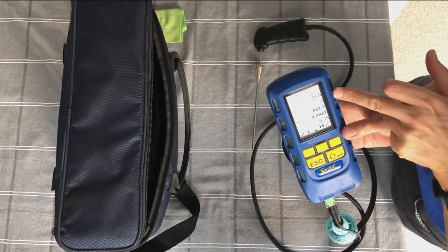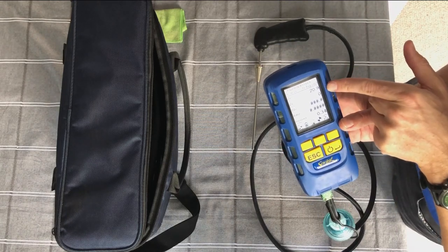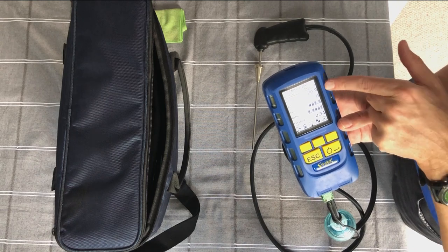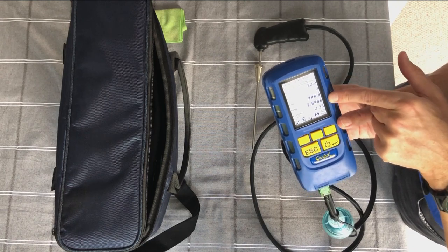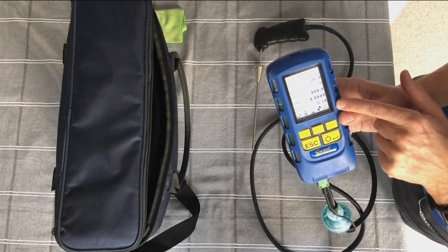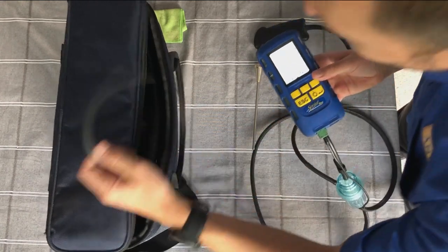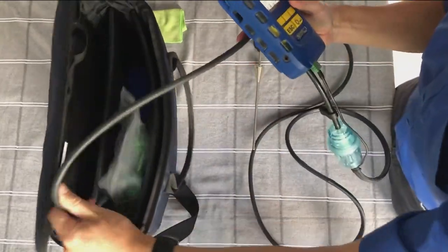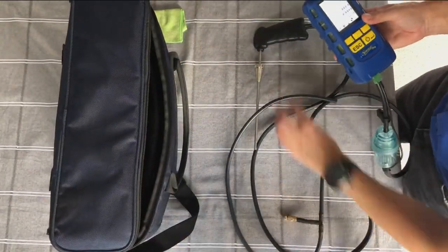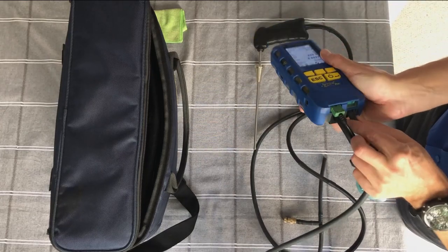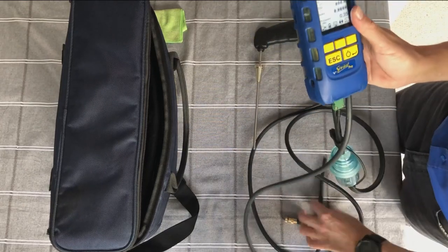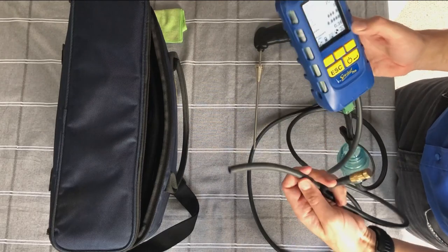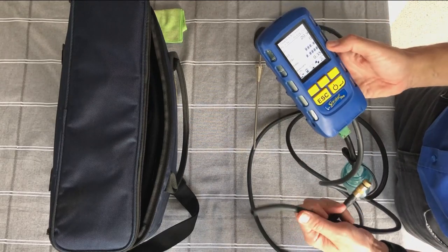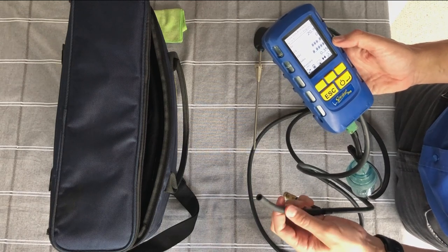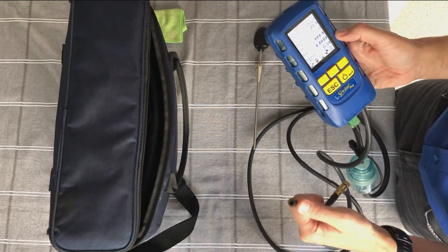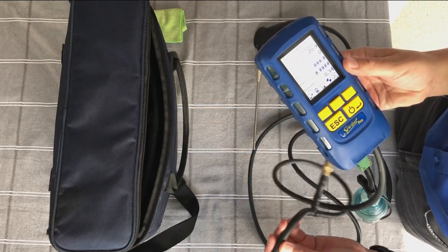The front page that we've got here shows you the most popular or most commonly needed information. So the oxygen reading, the CO, the CO2 and the ratio. We've also got a pressure reading. So if you want to take some pressure, here's my pressure relief valve, which I'll talk about in a second, but you can connect that up, push it onto your pressure spigot, and you can actually be taking a pressure reading whilst you're doing your flue gas analysis. So for certain boilers, I think that's needed. It's not most of the time, but if you need to take a working pressure and operating pressure at the same time as your flue gas analysis, you can do it.